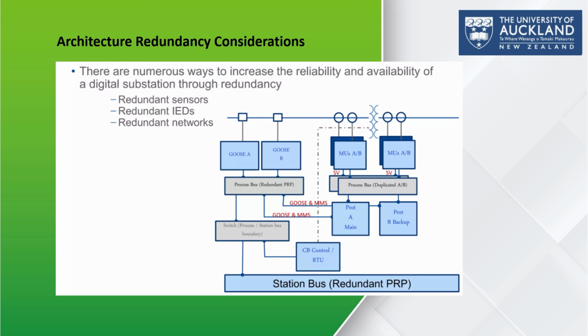Devices such as GOOSE A-B publishers, merging units, protection relays, and the switch at the boundary between the process bus and the station bus all participate in this redundant communication architecture. Messages like GOOSE and MMS are transmitted through both A and B networks, so the control, monitoring, and protection functions always receive reliable data, right?